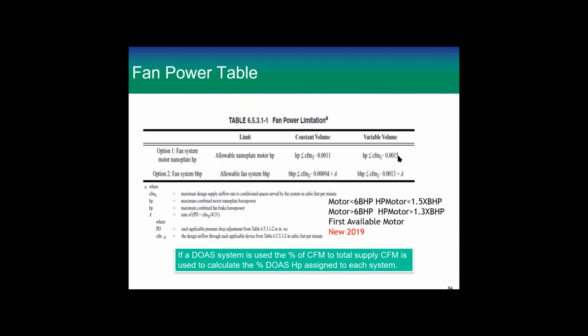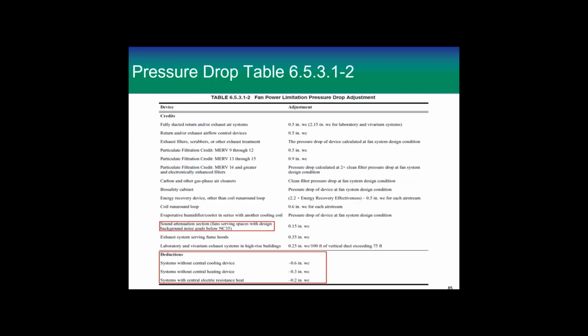So if you're using a DOAS system, suppose it supplies several rooms, and each one of those rooms has a percentage of the CFM. You have to put a percentage of the fan horsepower of the DOAS into that space. So suppose the DOAS is serving 2 different air handler systems, or more. You have to percentage out that CFM between them and use that horsepower by that same percentage as the CFM. So it would just be another fan you added, just like you would your exhaust fan.